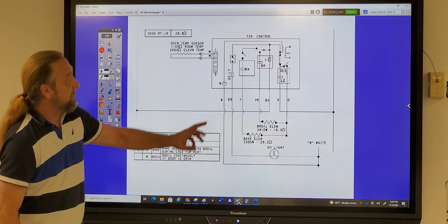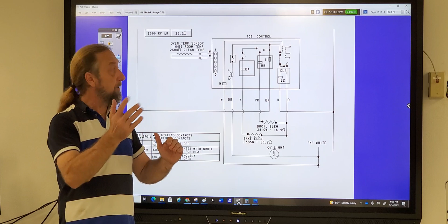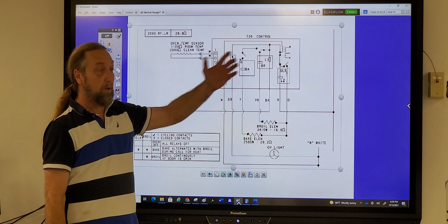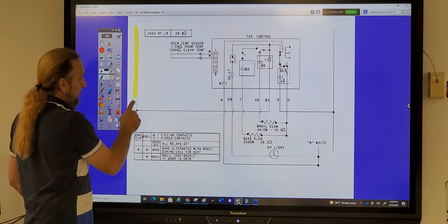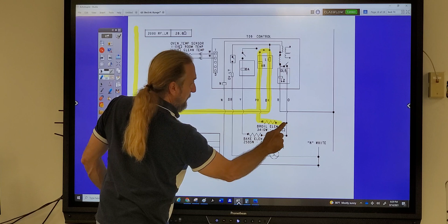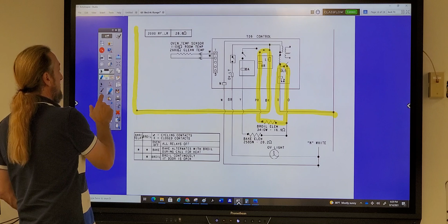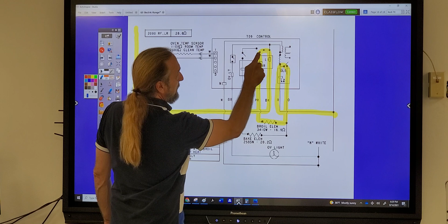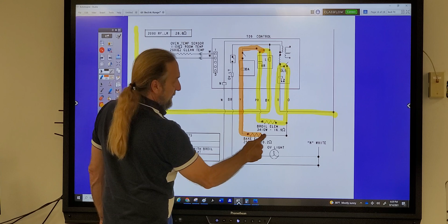But those contacts cycle. In other words, when we're cooking, the double line break relay stays on the whole time we're cooking. If we're broiling and the element needs to cycle on and off, that's done through that relay right there. That relay will open and close, cycling the element on and off. If we're baking, we go between the broil element, which here's the broil circuit, and I'll do them different colors. We go to the broil element, and it comes here and down and through the broil element, through the double line break and out. Now, what happens is it's going to switch to bake, and then this relay here will turn off the broil and switch to the upward position and go through bake here and out that way.